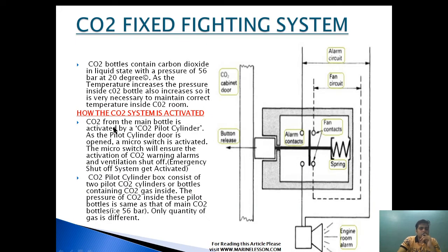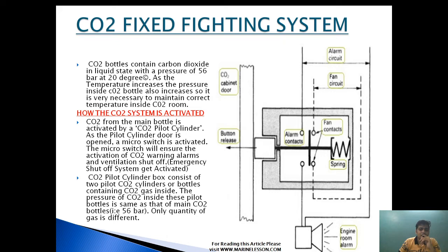The CO2 from the main bottle is activated by the CO2 pilot cylinder. As the pilot cylinder door is open, a micro switch is activated. This micro switch ensures the activation of the CO2 warning alarm and ventilation shutoff. The alarm allows engine room personnel to know that the CO2 alarm has gone on and they should immediately evacuate the engine room. The fan will go off to prevent the CO2 from being dispersed by the exhaust fan outside.